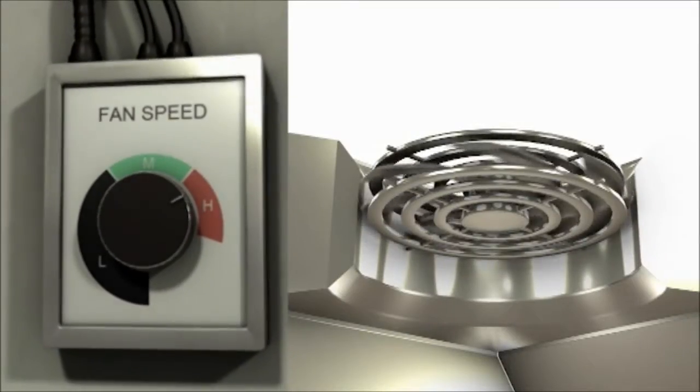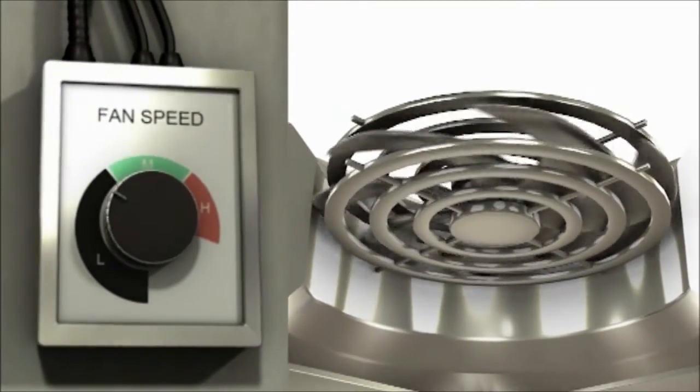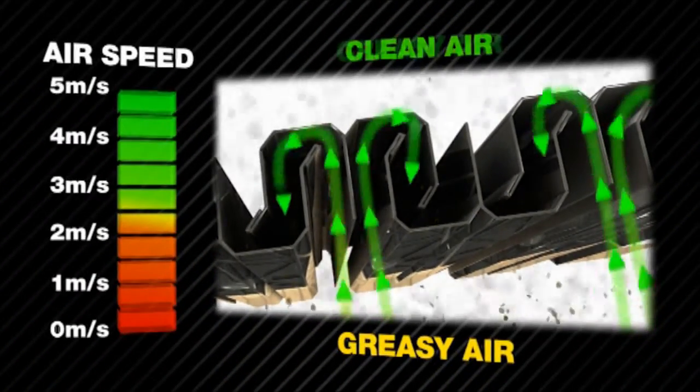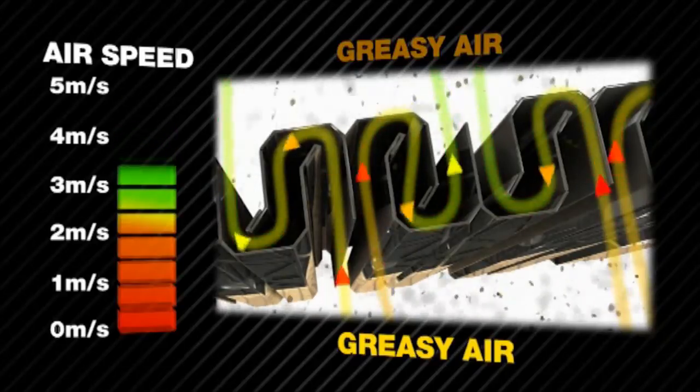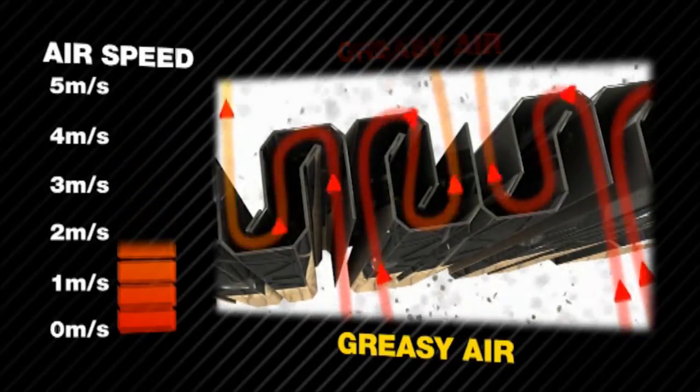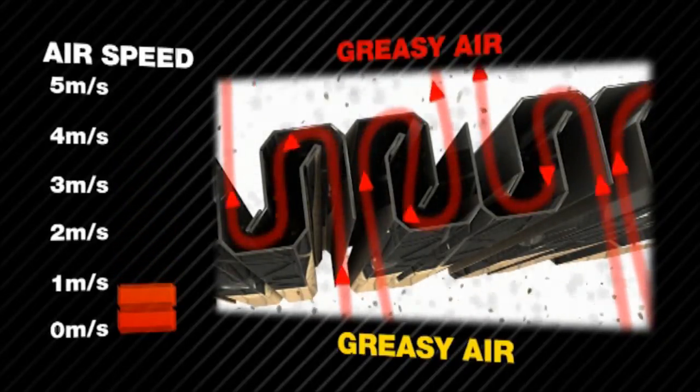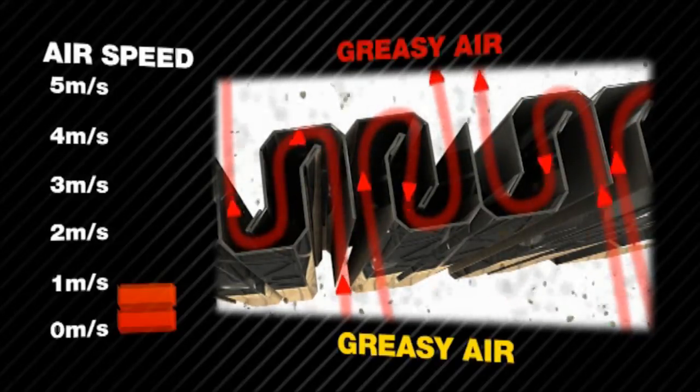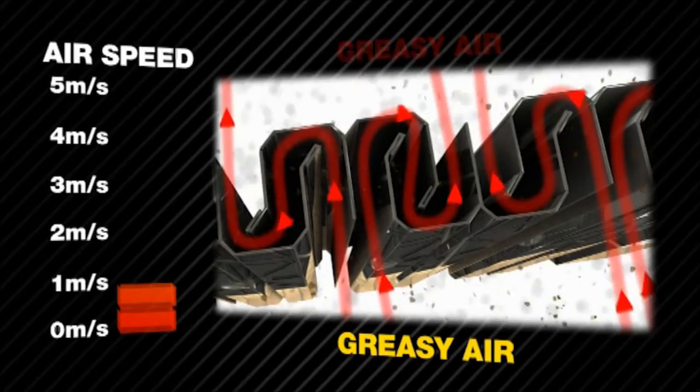Some energy saving systems simply reduce the extract fan speeds at low periods of cooking. This will cause the air speed to drop dramatically through the filter. The result of this reduction in air velocity means the filter no longer works efficiently, as the molecules of grease are no longer forced out of the air stream and onto the inside wall.